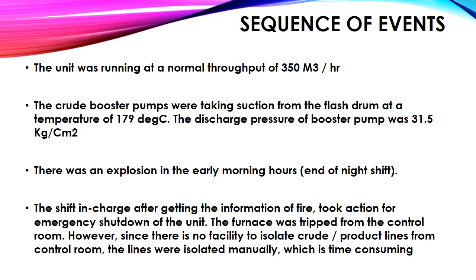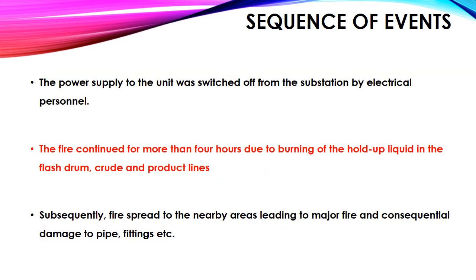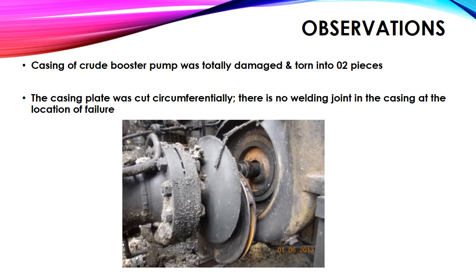The shift in charge, after getting information of the fire, took action for emergency shutdown of the unit. The furnace was tripped from the control room. However, since there is no facility to isolate crude product lines from the control room, the lines were isolated manually, which is time consuming. The power supply to the entire unit was switched off from the substation by electrical personnel. The fire continued for more than 4 hours due to burning of holdup liquid in the flash drum, crude and pipelines. Subsequently, the fire spread to nearby areas, leading to major fire and consequential damage to pipe fittings, etc.